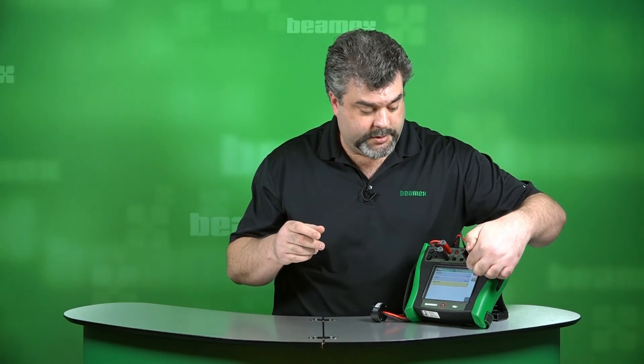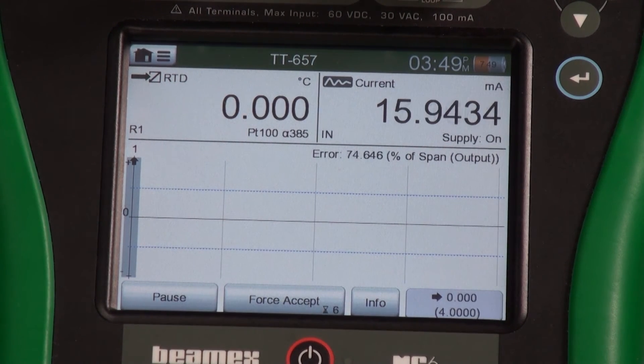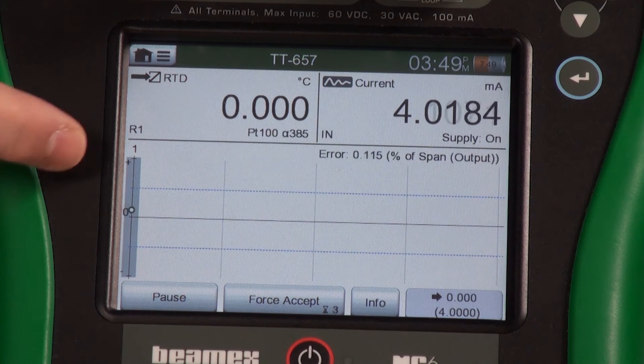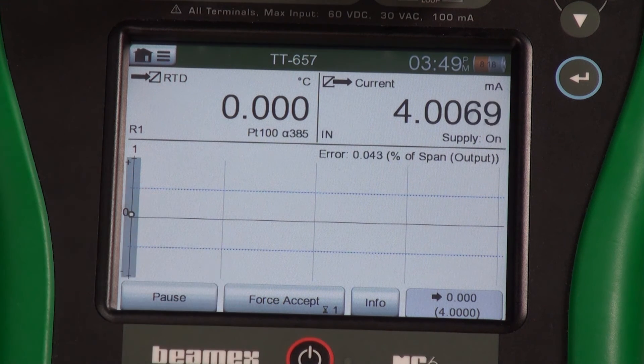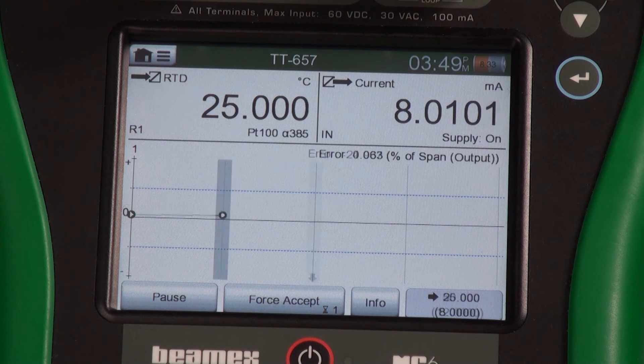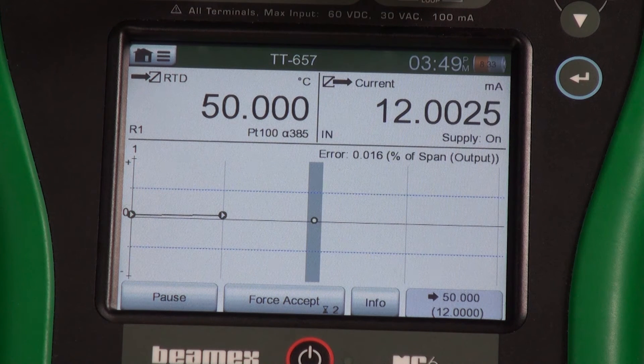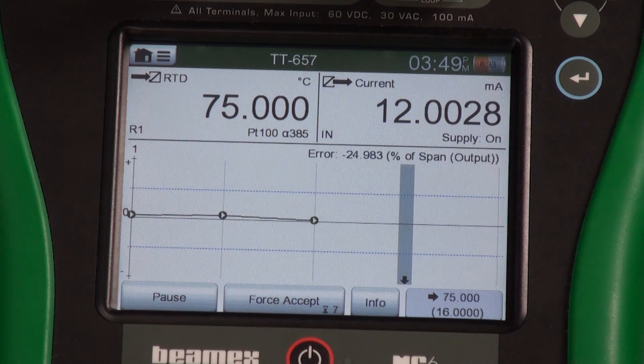The loop can be returned to automatic control — we are done. At this point, we simply hit X to exit out of communicator mode and finish up with our as-left. Now that we've finished doing our trim, we can do our as-left test. To start that, we simply hit the start button. The same series of events will occur — we'll start off with our zero point. We have a 10-second timer in between each step, and on the bottom right it shows us what test point it's heading to next. At any time, you can see the live error reading right above the graph.